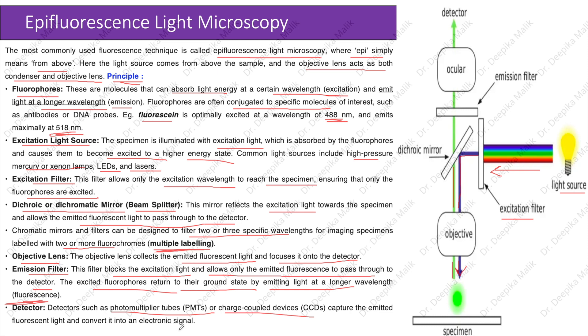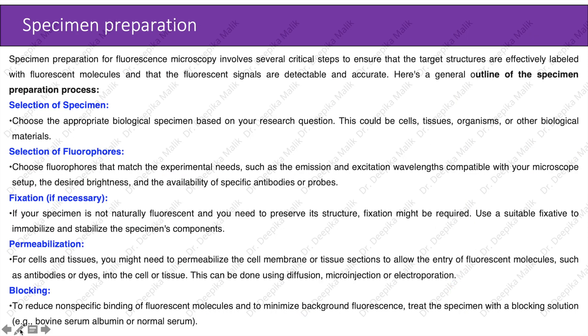The excited fluorophores return to the ground state by emitting light at a longer wavelength, known as fluorescence. Detectors such as photomultiplier tubes or charge-coupled devices capture the emitted fluorescence light and convert it into an electronic signal. Specimen preparation for fluorescence microscopy involves several critical steps to ensure that target structures are effectively labeled.